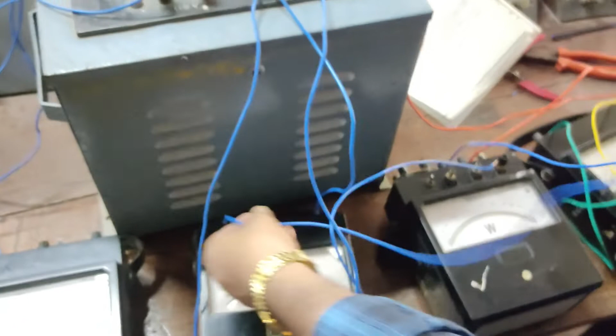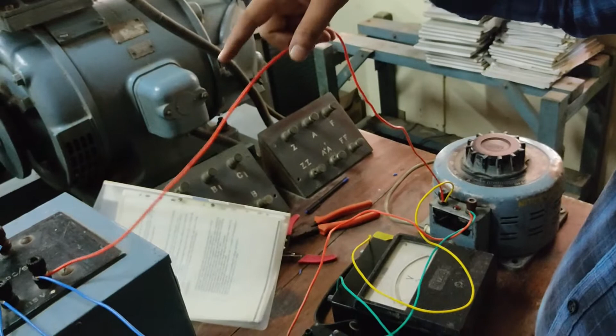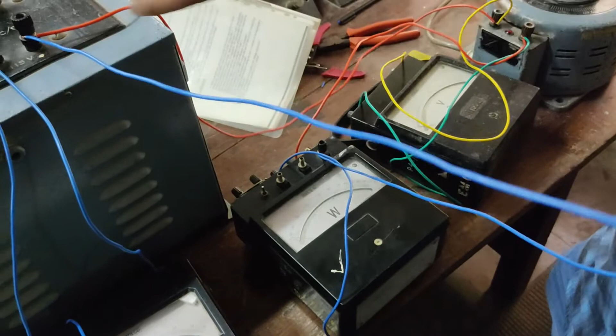And again from the line terminal to the current coil, one more terminal goes to the ammeter, 0 to 10 ampere or 20 ampere, which you can connect based on our rating, and then one more terminal of the ammeter goes to one of the input terminals of the two winding transformer. And next, the autotransformer neutral is connected by one wire to the input neutral of the two winding transformer, and the wattmeter voltage coil is also connected to the neutral of the input supply of the transformer. Okay, so this is about the input side. To measure input voltage a voltmeter is required, for input power a wattmeter is required, and for input current an ammeter is required.